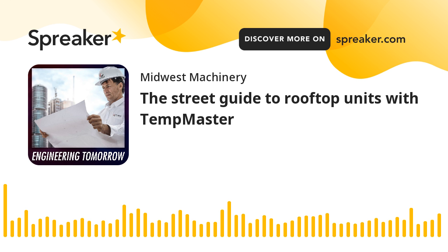And then the product itself has to be designed with a lot of things in it to make it easier to service the unit. And that starts with, how do you make sure that routine things like changing filters are easy? One of the options that we've introduced is a differential pressure transducer across the filter banks. So now you can actually measure the pressure loss across that filter bank. And as that pressure increases, you know that it's time to change your filter. You don't have to do it periodically anymore. You can actually do it based on the filter loading. And then making sure that the refrigeration system is easy to manipulate as well. What are some things, Eric, that we've done on the refrigeration system?